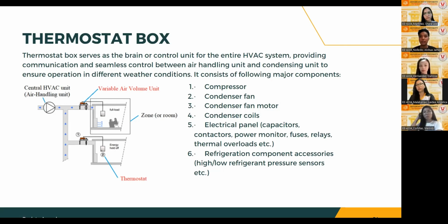Moreover, the thermostat can display different error codes for problems such as AHU coil sensor failure, insufficient or loss of refrigerant, compressor overload, low and high refrigerant pressure, AHU coil freezing, and etc. Whenever an HVAC unit trips abnormally, the corresponding error is displayed on the thermostat box, which helps the technical staff in diagnosing the problem immediately and accurately.